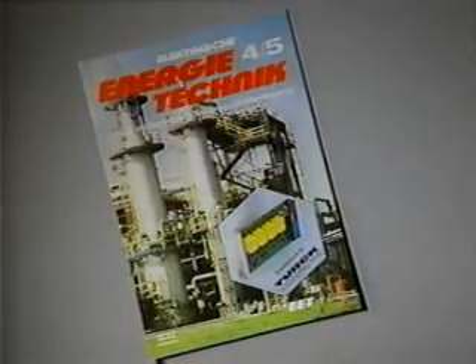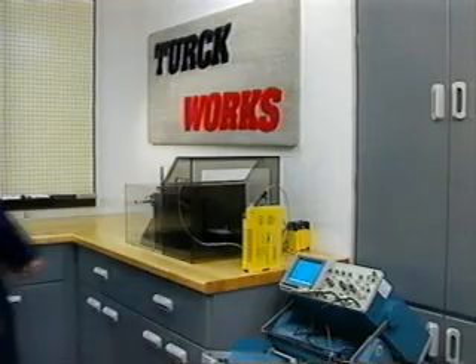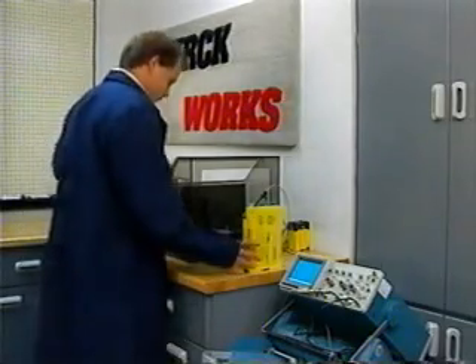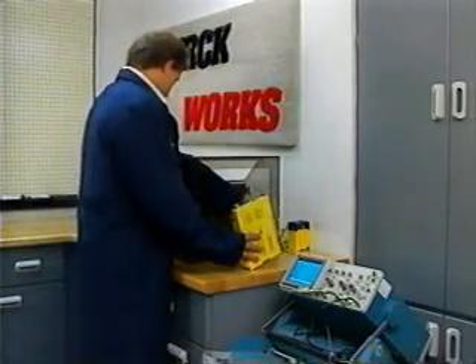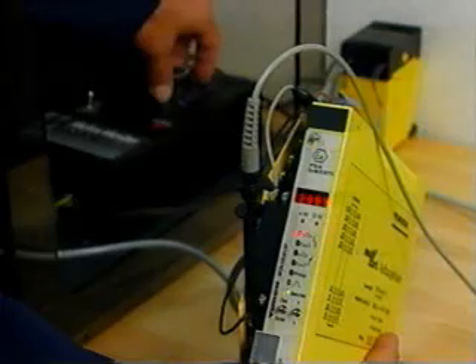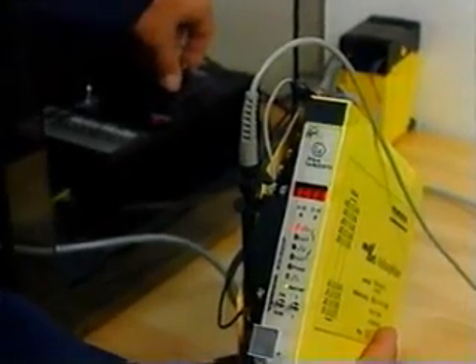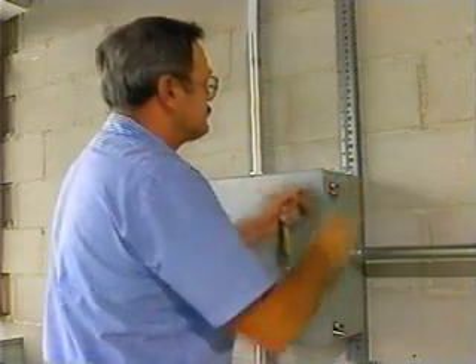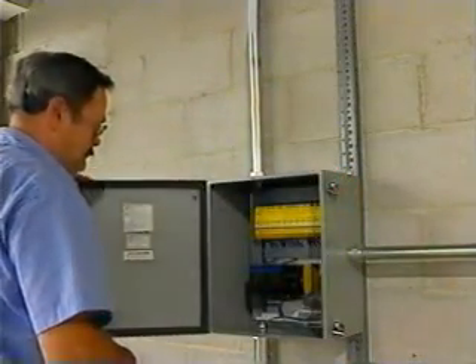Intrinsically safe devices bring advantages besides safety to hazardous areas. They are proven technology. The concept has been thoroughly researched, and intrinsically safe devices have been in use in Europe for well over 30 years. Devices with the intrinsically safe designation can be tested while hot. Their current cannot cause an explosion, so there is no need to shut down a hazardous area to diagnose a problem. And the vast majority of these devices require no maintenance.